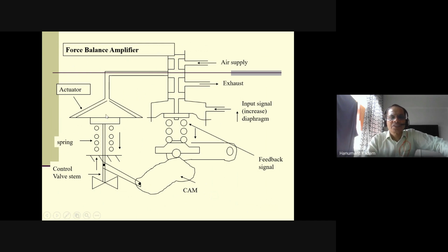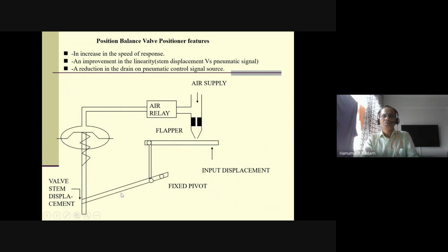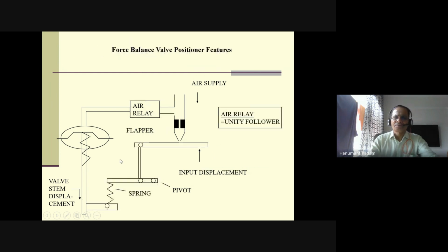So here you can see this is the valve, spring control valve, and this is the link of the control valve, and through this cam it is connected to this mechanism, feedback signal, and it is a balance. The position balance, same thing. Here is a valve, this is a valve, stem, fixed pivot, flapper nozzle system here. So these were earlier mechanisms, and still in the pneumatic positioner it is there. This part, flapper nozzle system or relay.